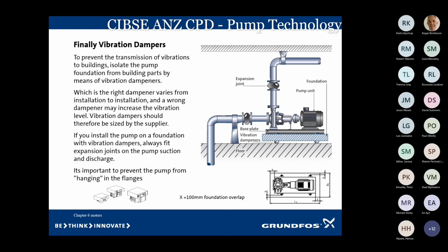This is why, in cases where we don't want vibration being transferred down, we use an inertia base and the vibration mounts. When we use the mounts, make sure that they're sized correctly and that we don't get them mixed up. All the vibration mounts come at different spring levels, different weight loads. If we get them incorrect, then we can get the pump tipping. And again, you'll have issues in here.